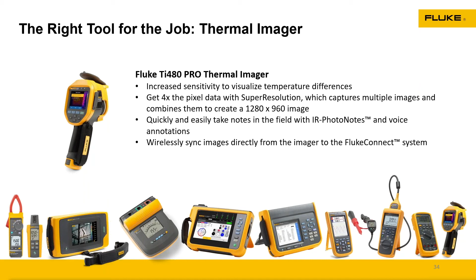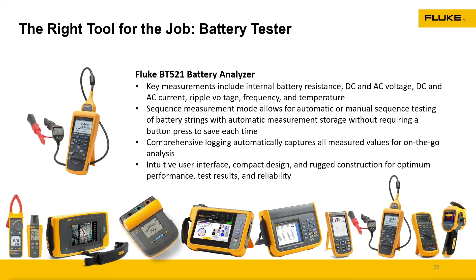Now, we did mention briefly the battery storage systems. You'll need a tool to analyze that each one of those batteries is ready to go and working correctly. So have a battery analyzer on site. That'll help you determine that, especially during the commissioning aspect. Unless you know the battery manufacturer's information, you'll want to do a pre-analysis and testing so that later on we can start doing some trending analysis of those batteries, making sure that they're working correctly. But a good battery analyzer is going to allow you to validate and determine that.